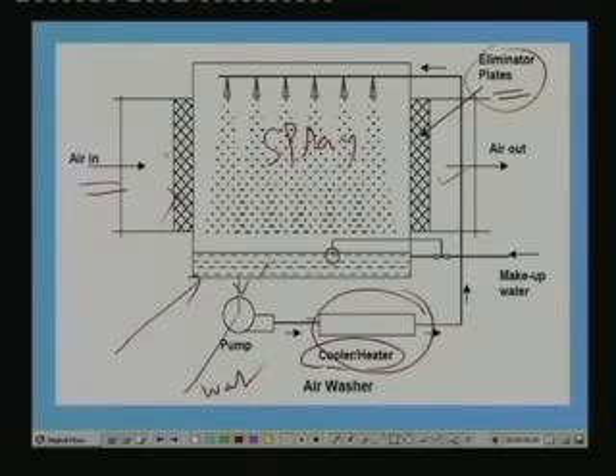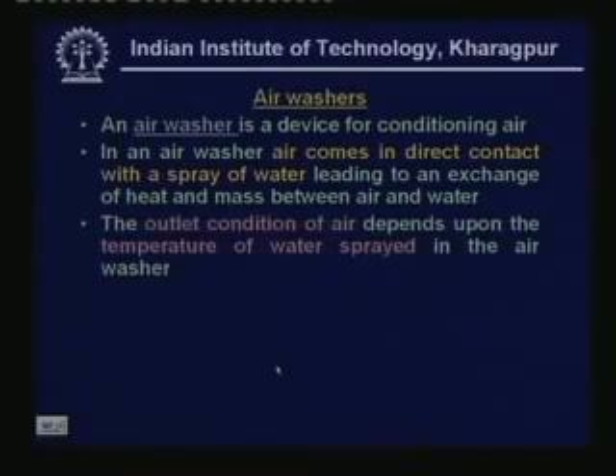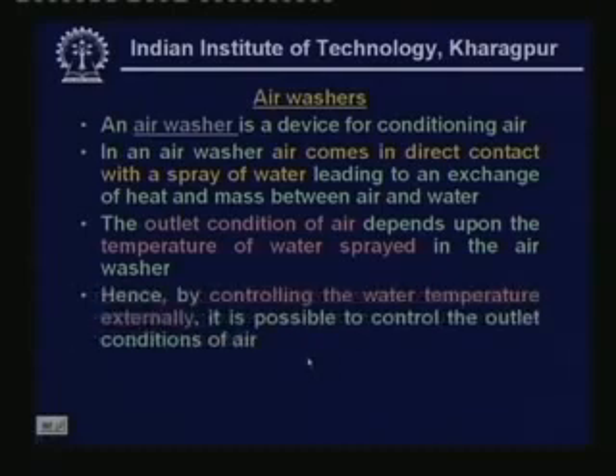So, air enters, let us say, through a filter, and it comes in contact with the spray of water, and during this contact either sensible or latent heat transfer takes place or both take place, depending upon the temperature of the water. So, by controlling the temperature of the water, you can achieve different exit conditions. This unit is known as an air washer. The outlet condition of air depends upon the temperature of water sprayed in the air washer. Hence, by controlling the water temperature externally, it is possible to control the outlet conditions of air.